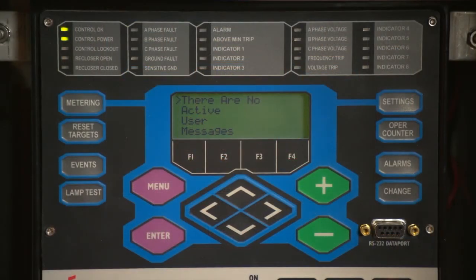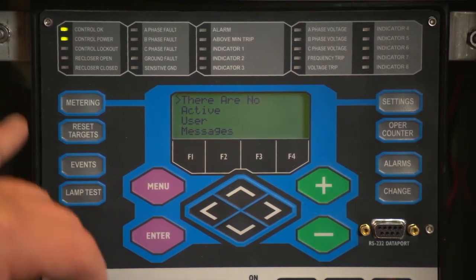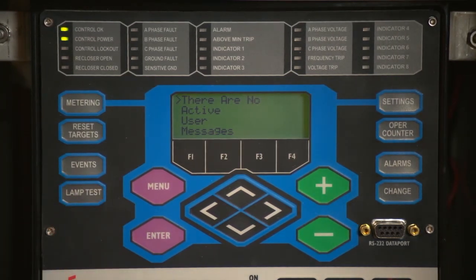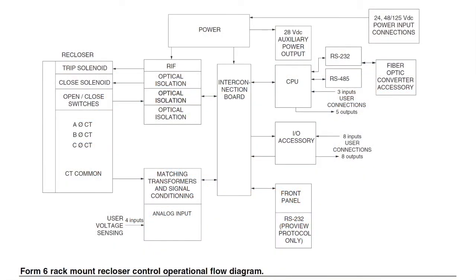Theory of operation. Current sensing is provided by 3 current transformers located in the recloser and interface to the Form 6 recloser control via control wiring. This wiring also supplies trip, close, and recloser status and connects to the recloser interface or RIF module to provide isolation for reliable operation. A functional block diagram of the Form 6 recloser control is shown.